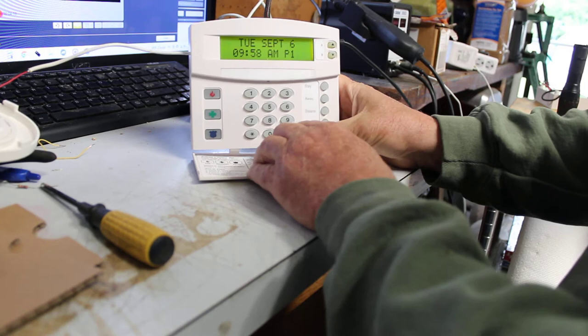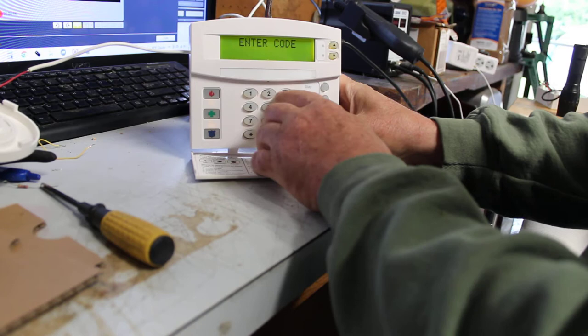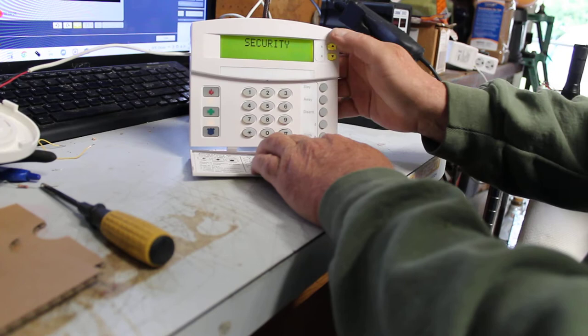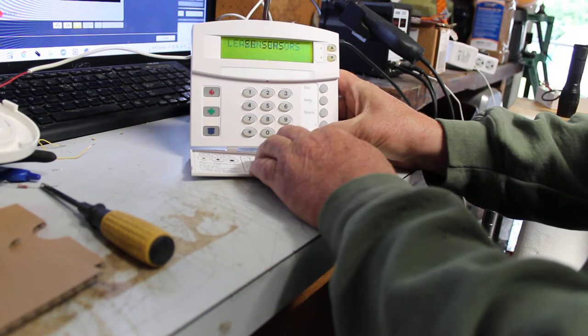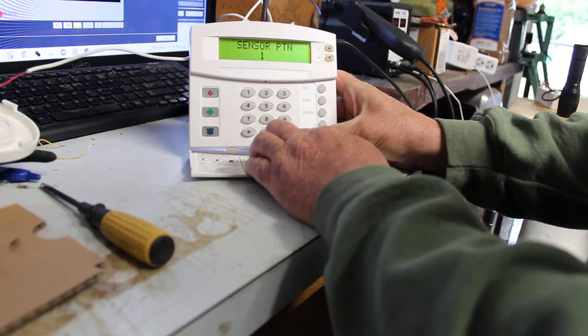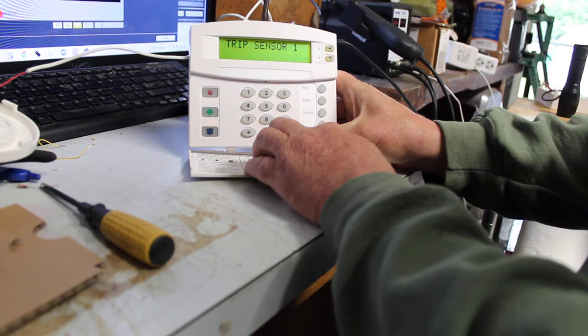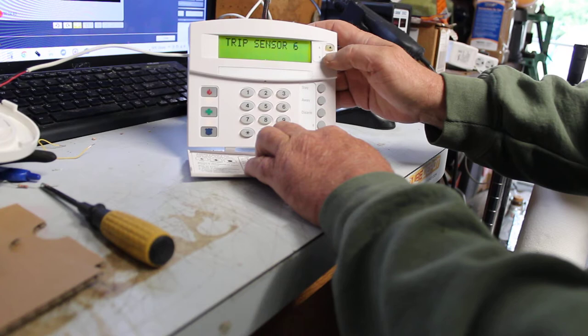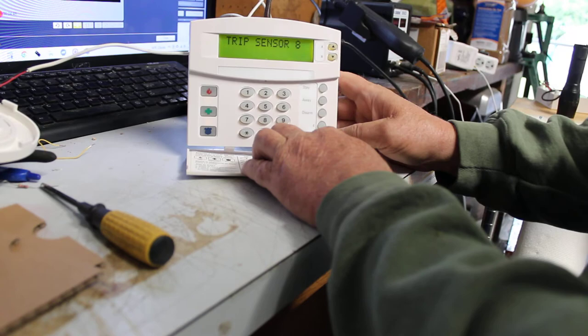Let's put this to the side for now. Let's go into program and program zone 8 as a fire. We go 8-4-3-2-1-0-0, system program, hit the pound, go up to sensors, sensors, hit the pound, learn sensors, hit the pound, partition 1, hit the pound, sensor group is 2-6, hit the pound. Now you want to go up to zone 8 because that's what is used for fire alarm and heat detectors on a Concord 4 and a Concord Express.